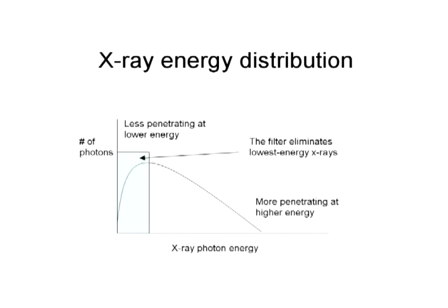Remember what I said earlier, that X-rays are given off with energies going from 0 all the way up to the maximum energy that they can have, basically the number of electron volts that the electrons pick up. The lowest energy X-rays don't do anything, so why let them intersect your body at all? What we can do is to put a chunk of aluminum in front of the X-ray tube, and that aluminum will filter out the low energy X-rays, and it will only allow the X-rays through that will actually contribute something useful. So by increasing the filtration, we make the X-ray beam a little bit harder, and that results in less dose, or it reduces the radiation dose to the person who's near the X-ray machine or the patient who's being irradiated.